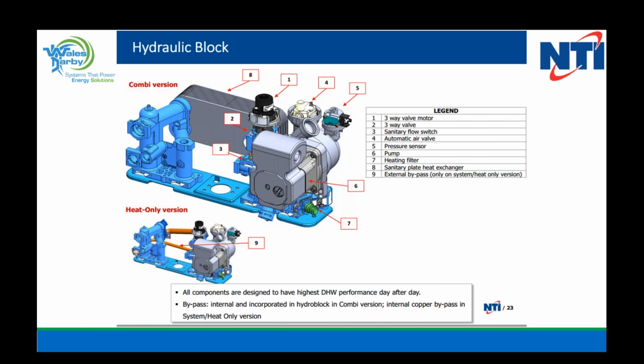So here's the hydraulic block in the Combi version on the top and the heat only version on the bottom. Number 8, that is the sanitary plate heat exchanger. That's the flat plate heat exchanger. That's where we're going to make our heat transfer and make our domestic hot water. So the only difference between the Combi version and the heat only version is that the heat exchanger is not installed on the heat only side, but we have an external bypass. Everything else is basically the same.